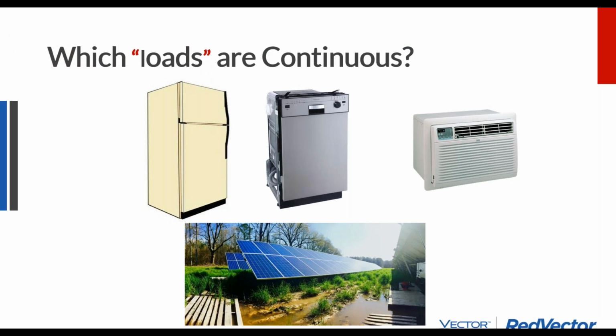So think about loads in terms of which loads are continuous versus non-continuous. And it can also come down to, maybe a dishwasher is a non-continuous load, but if it shares a circuit with other appliances, it turns into a continuous load for that circuit rating. Air conditioners, refrigerators, even solar arrays would be treated as continuous loads.